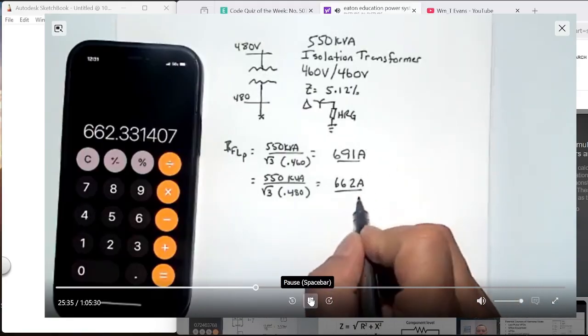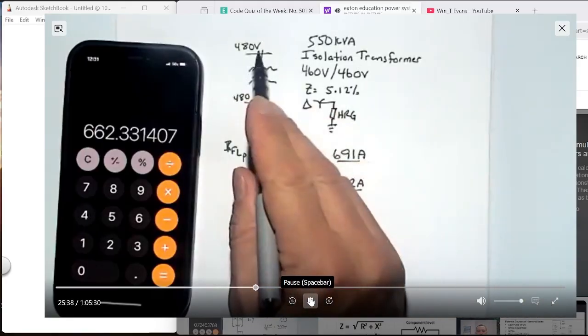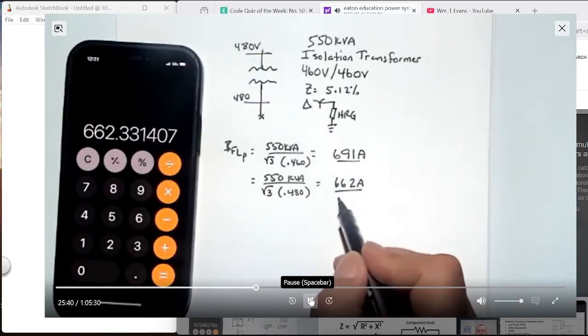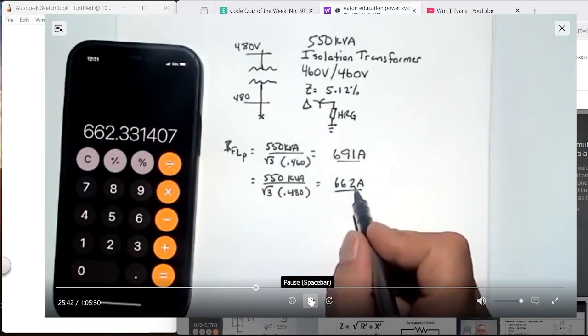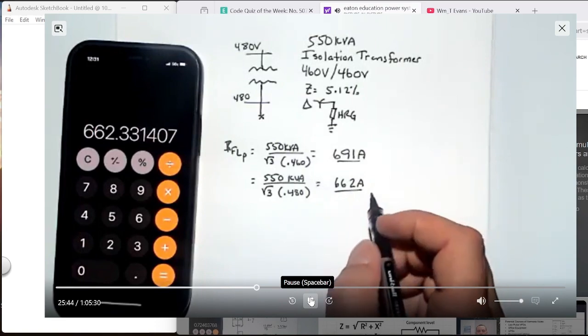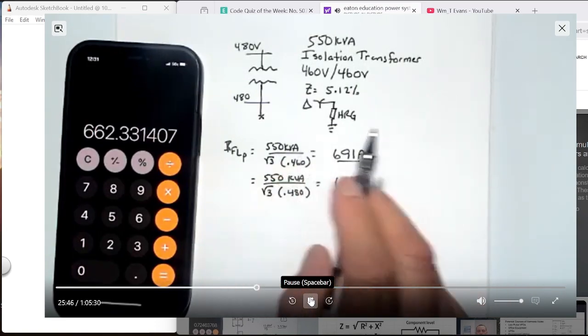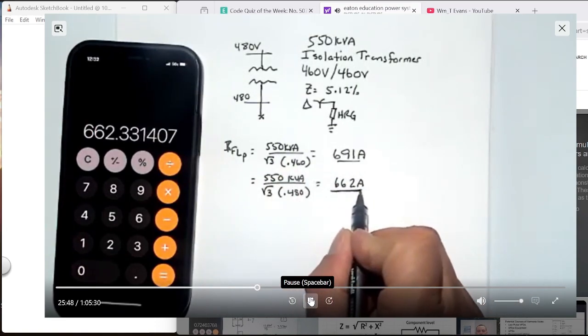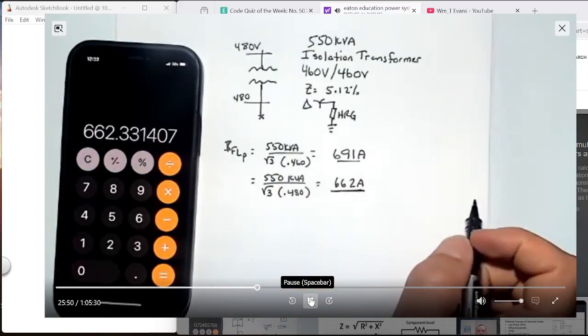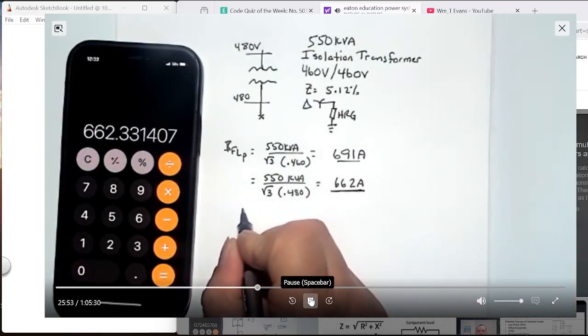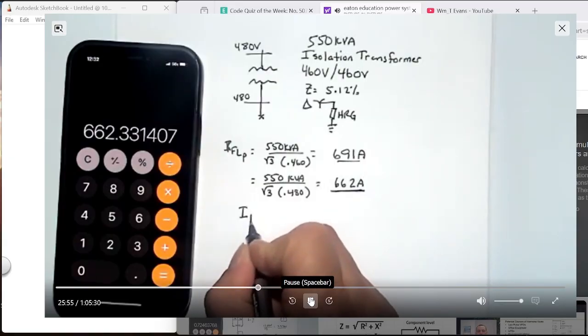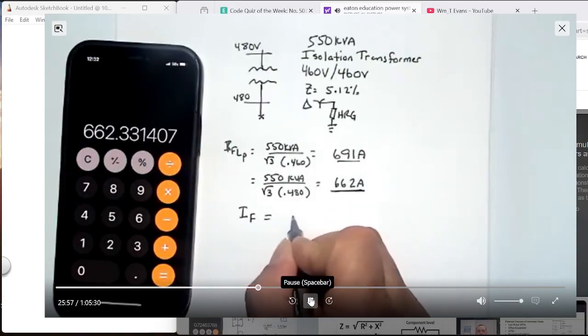So anyway, again, sizing the breaker here, we might size it for 660. Well, it's not going to be exactly that. It's going to be something less or a factor of that, even a little bit more, depending on how our protection scheme is done. But we're going to typically base it on that because we know we're applying it at 480 volts.